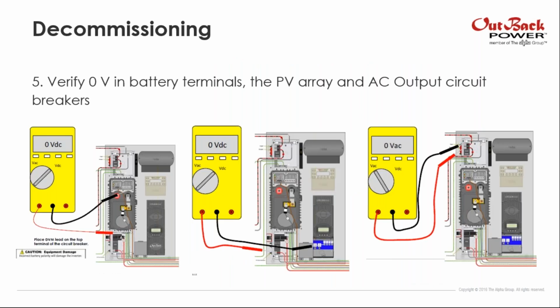And finally, once we have removed all the power from our system, we will need to verify that we have 0 volts in the battery terminals, in the terminals of the PV array, and the terminals of the AC output circuit breakers. So when I check that I have 0 volts, now I can manipulate my system with confidence.